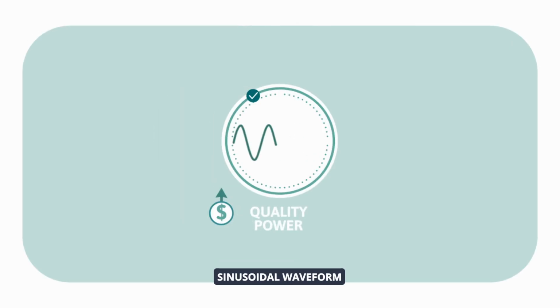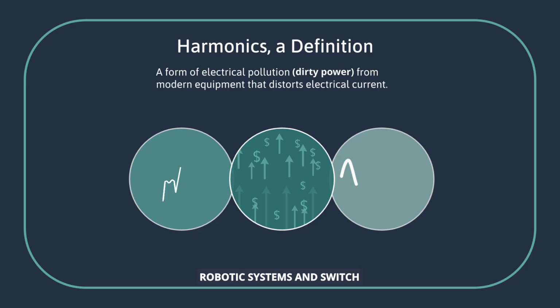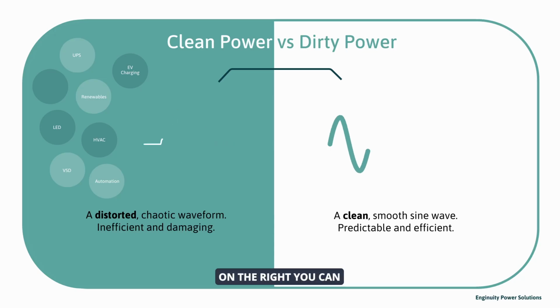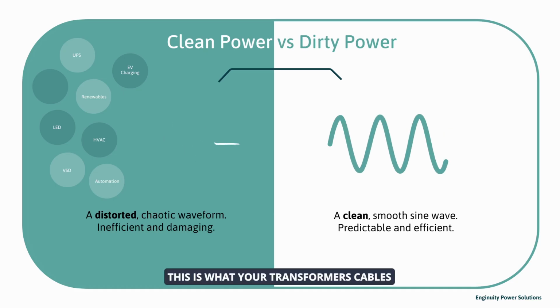In simple terms, harmonics are distortions in the electrical waveform caused by modern electronic loads. Your electrical infrastructure was designed for a smooth sinusoidal waveform. However, non-linear equipment such as variable frequency drives, robotic systems and switch mode power supplies distort that waveform. The result is unnecessary electrical losses and system stress. On the right, you can see clean, stable power. This is what your transformers, cables and motors were designed to operate on. On the left, you can see distorted power.